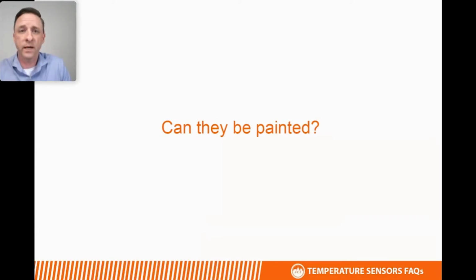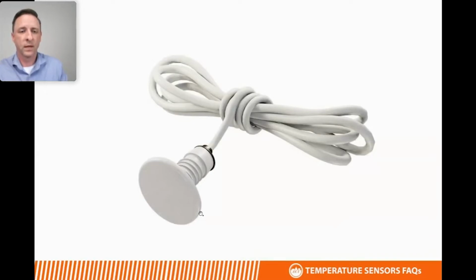And the most common question we get on those is, can they be painted over? And yes, on the screen you see a plastic button sensor, and they can be painted over. We've had people use drywall mud over top of these. It's going to affect the response time and the responsiveness to temperature changes, and there's no real way to determine how much that paint or drywall mud would affect that. The other thing we'll ask people to pay attention to is, if you paint over it, it might be very hard to find. So you may want to put on your drawings where exactly the sensor is, or indicate that otherwise, if the sensor needs to be replaced or serviced, or someone needs to know that location in the future.